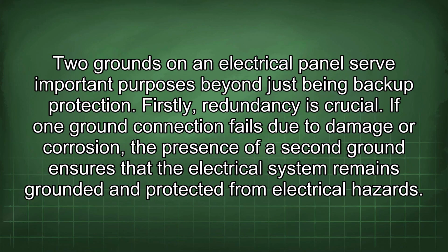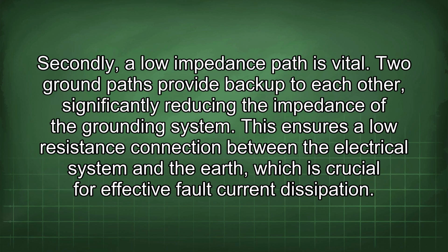Two grounds on an electrical panel serve important purposes beyond just being backup protection. Firstly, redundancy is crucial. If one ground connection fails due to damage or corrosion, the presence of a second ground ensures that the electrical system remains grounded and protected from electrical hazards. Secondly, a low impedance path is vital. Two ground paths provide backup to each other, significantly reducing the impedance of the grounding system.